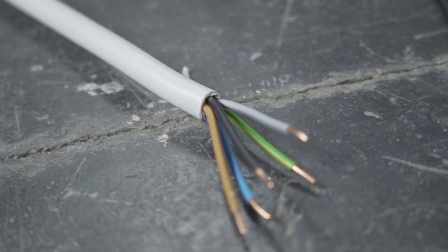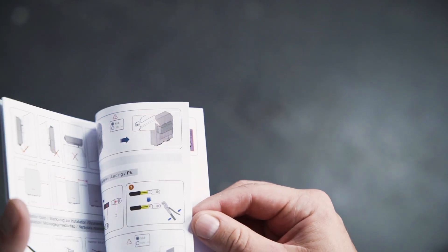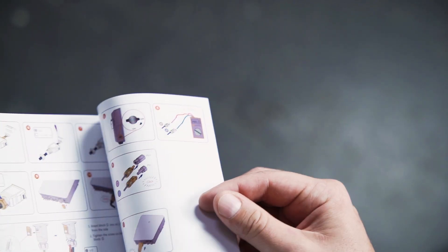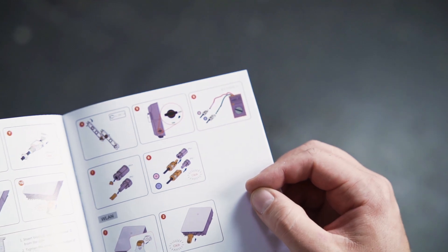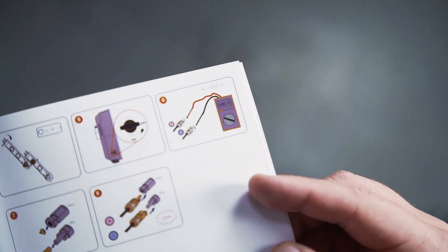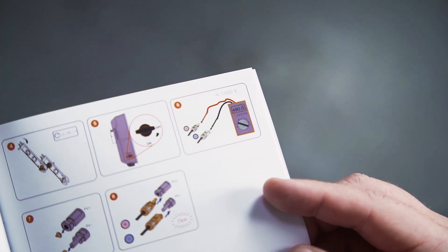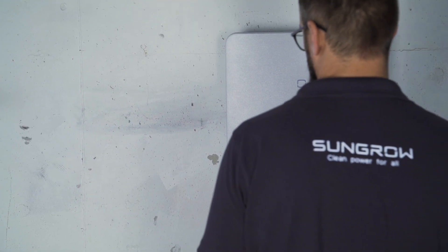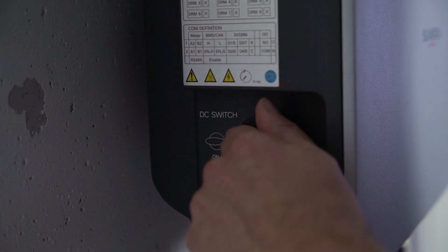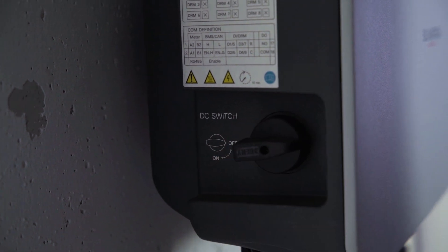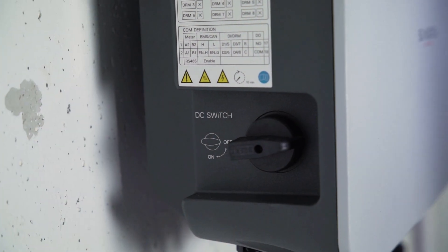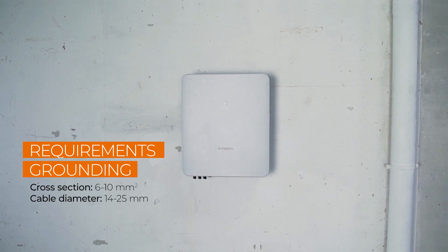Before installation, make sure by measuring that the cables are really voltage free. You will find all cable requirements and wire sizes necessary for commissioning in our manual. Furthermore, you have to set the DC switch on the left side of the inverter from on to off. Now let's continue with the installation.